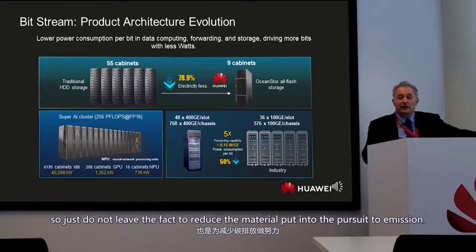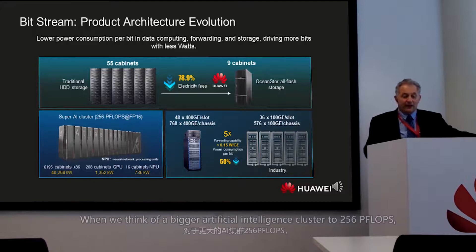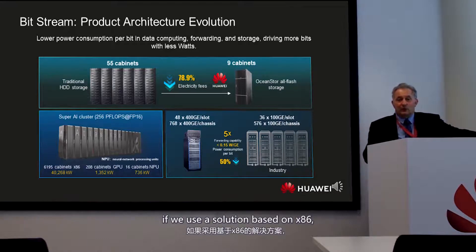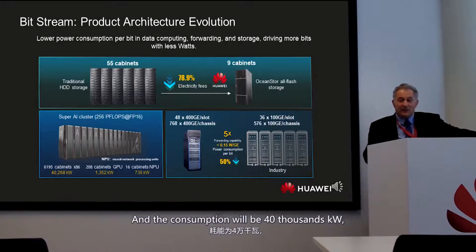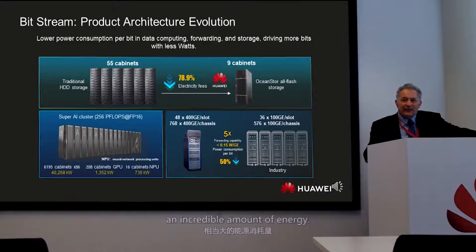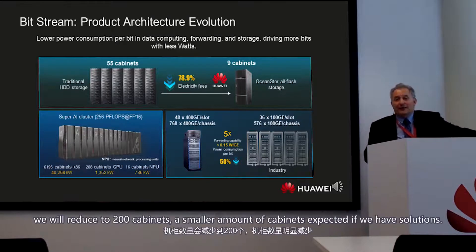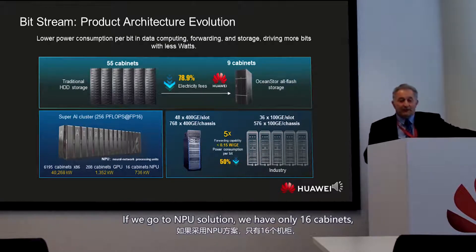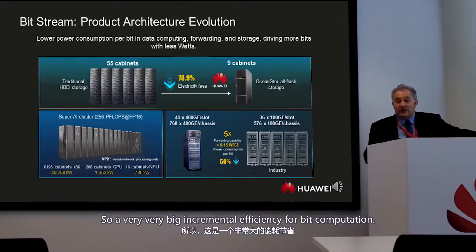The second point is computing efficiency. For a large AI cluster reaching 256 petaflops, an x86-based solution requires 6,000 cabinets consuming 40,000 kW. Moving to a GPU solution reduces this to 200 cabinets at 1,300 kW. Going further to an NPU solution reduces it to just 16 cabinets at 700 kW — a very significant improvement in computational efficiency.